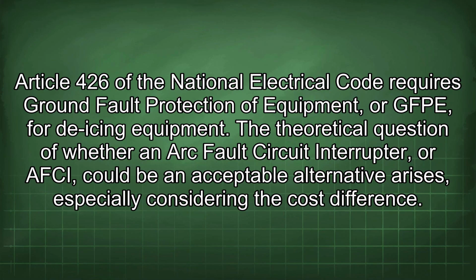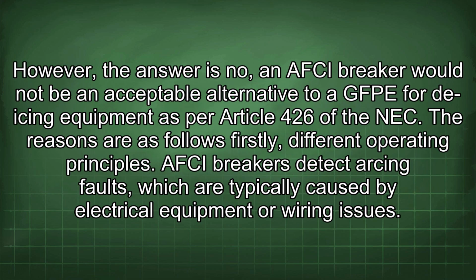Article 426 of the National Electrical Code requires ground fault protection of equipment, or GFPE, for de-icing equipment. The theoretical question of whether an arc fault circuit interrupter, or AFCI, could be an acceptable alternative arises, especially considering the cost difference. However, the answer is no. An AFCI breaker would not be an acceptable alternative to a GFPE for de-icing equipment as per Article 426 of the NEC. The reasons are as follows.